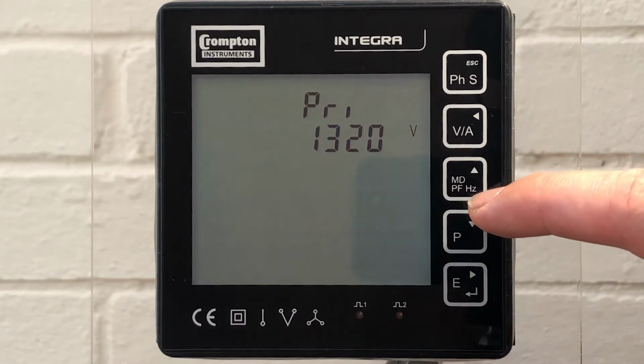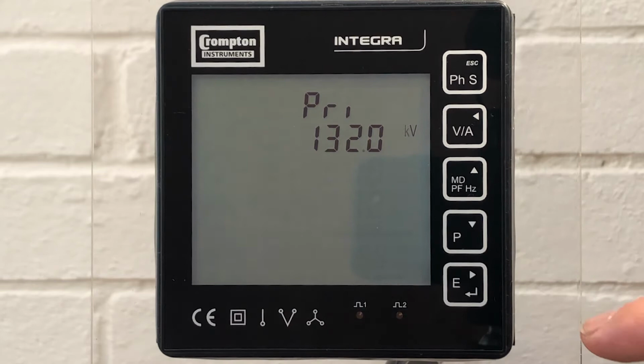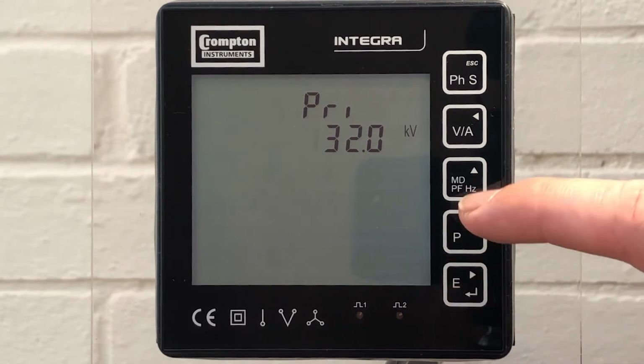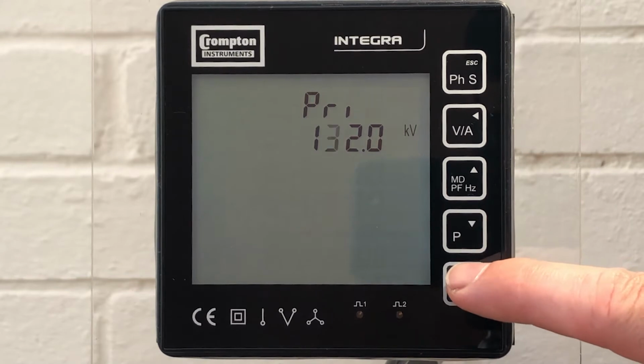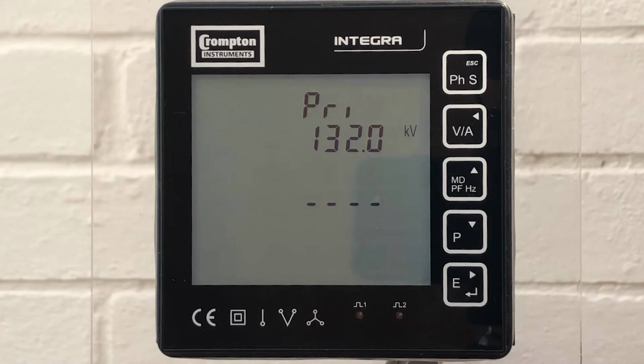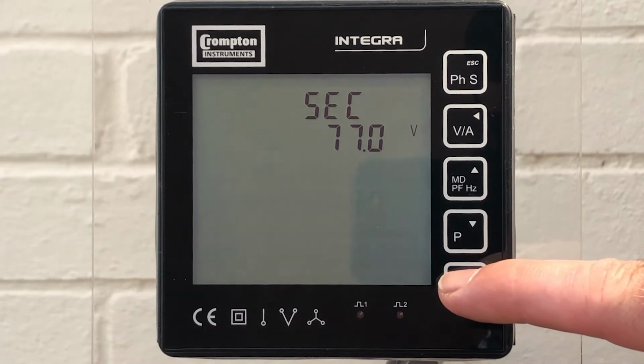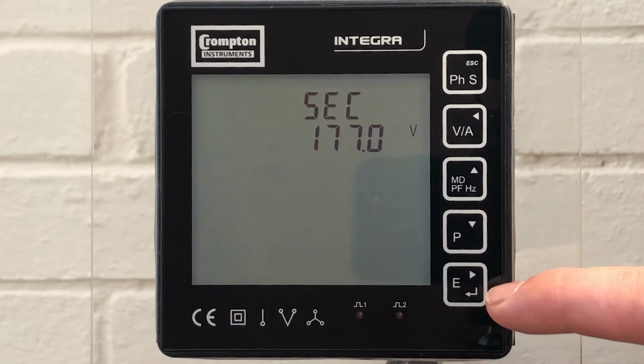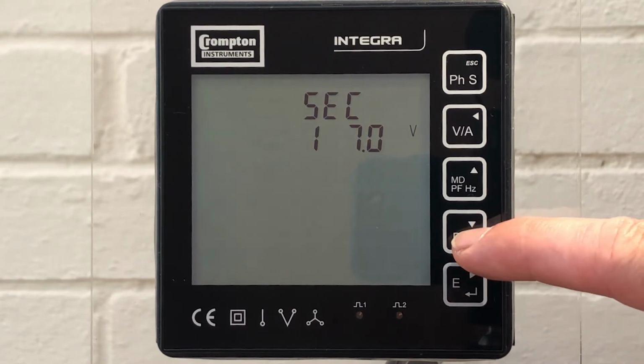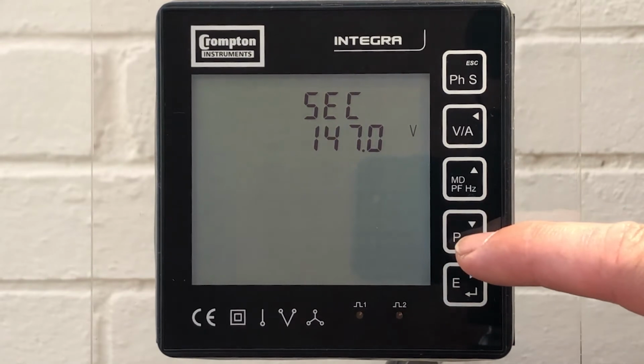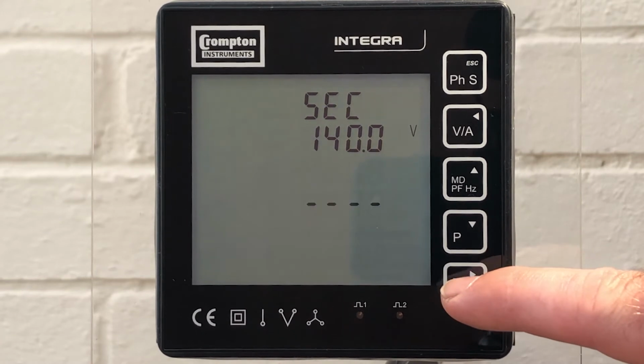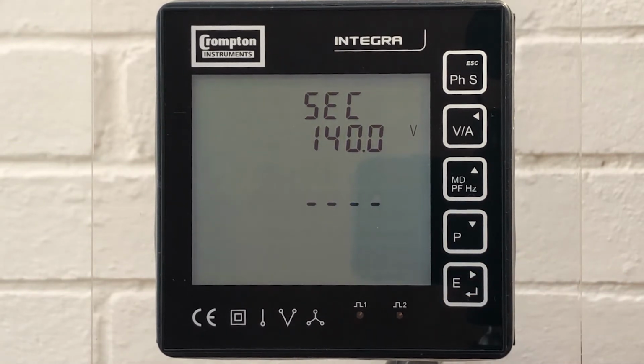So we hold down E, arrow up twice to get the decimal point in the right place, press the E button consecutive times until the screen displays 132 kV and says set. Press VA to escape from the primary voltage and arrow down to the secondary voltage selection. If, for example, your secondary voltage was 140 volts, repeat the same sequence as the primary setting and set the secondary voltage.